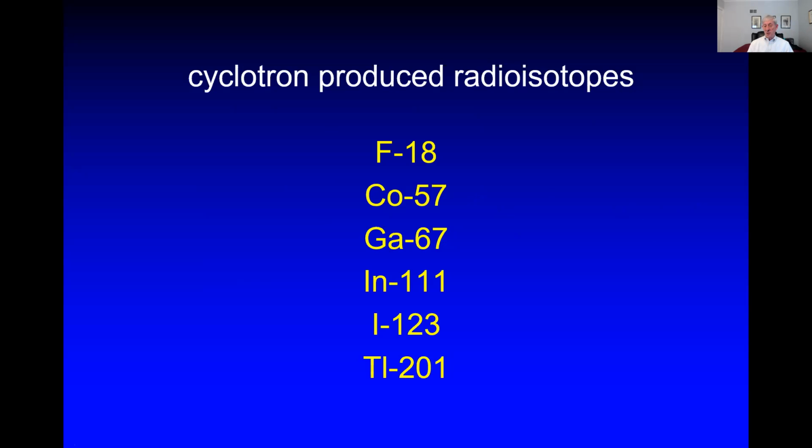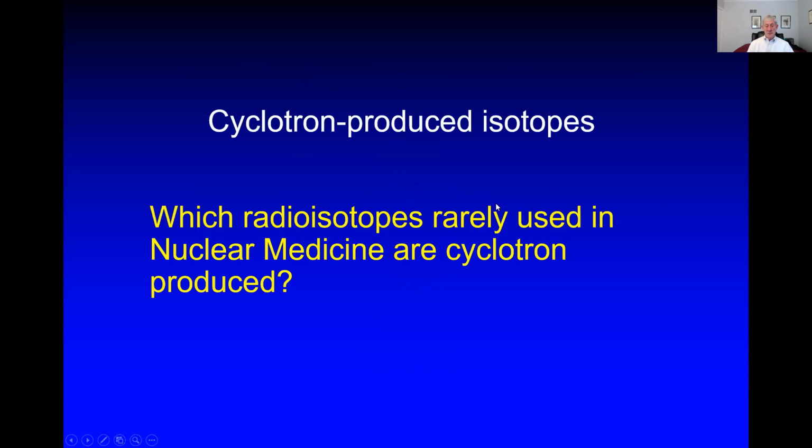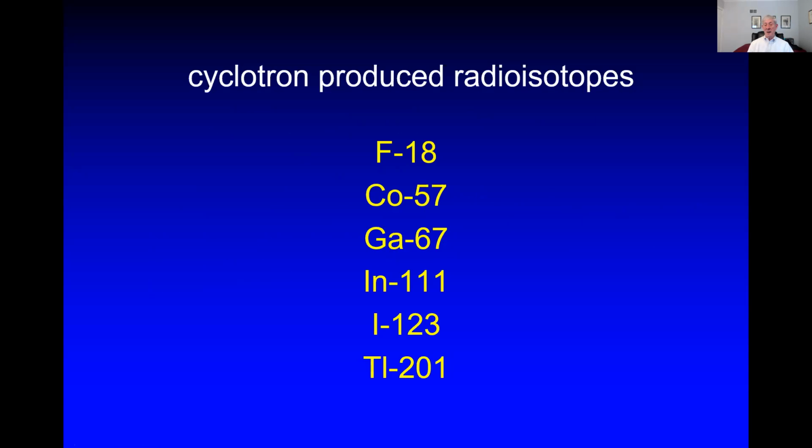And it's also one of the dose calibrator sources that everybody uses because it simulates technetium and energy, 122 versus 140. And we make the assumption that if our equipment works with cobalt, it's going to work with technetium. Pretty valid assumption. Now, those are the 6 that are commonly used.